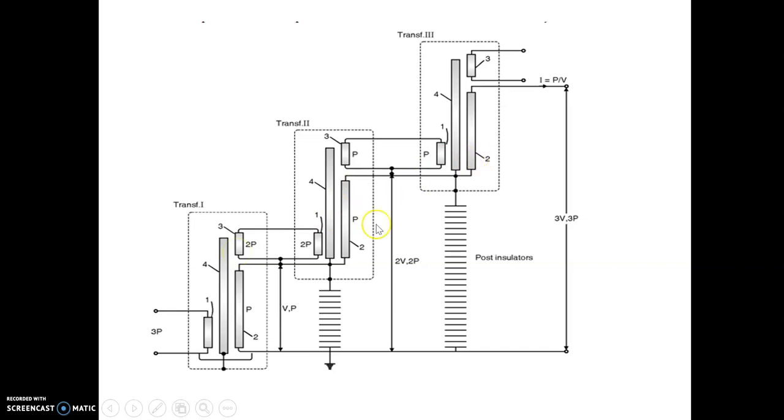So all these 3 transformers are 3-winding transformers. So 3 windings, or tertiary winding, or the balance winding. This is also called balance winding. So you can see here 100 volt you are giving. This must be 100 volt only, because this 100 volt will give the excitation to the primary winding of the second stage, and then this 100 volt will be raised to 100 kilovolt.